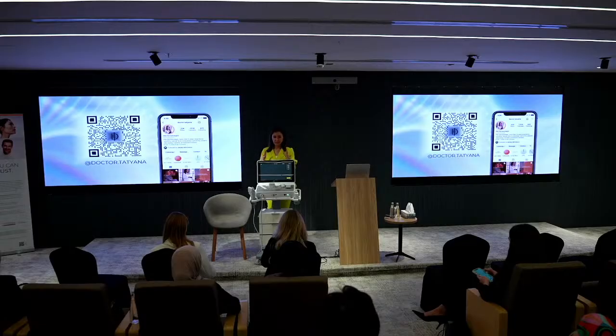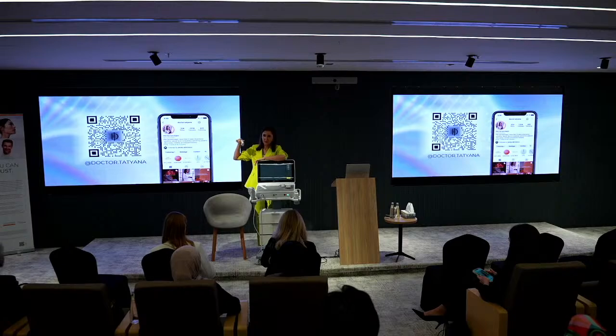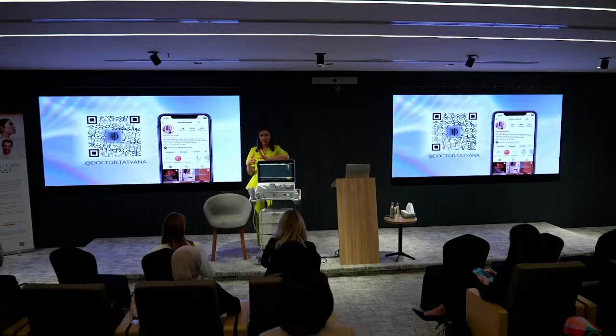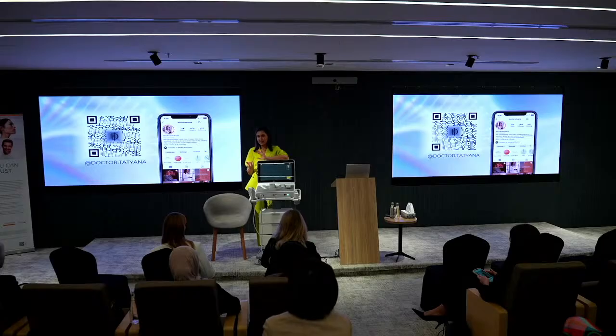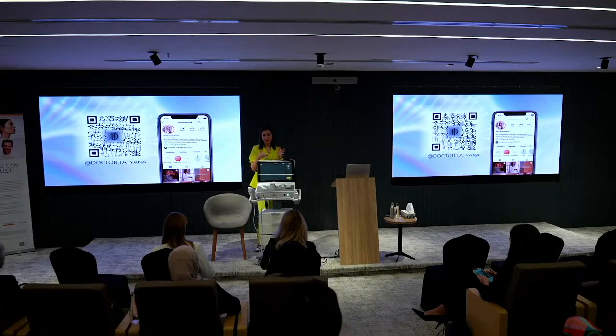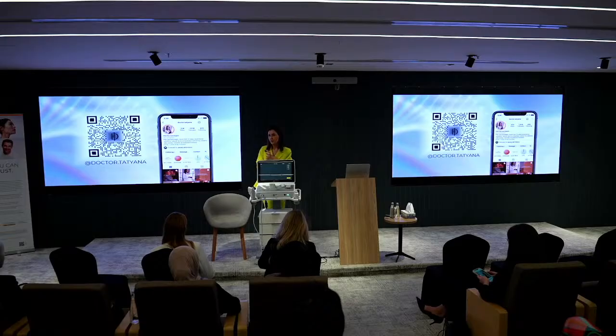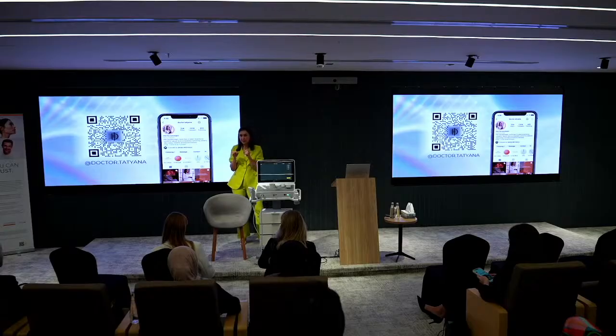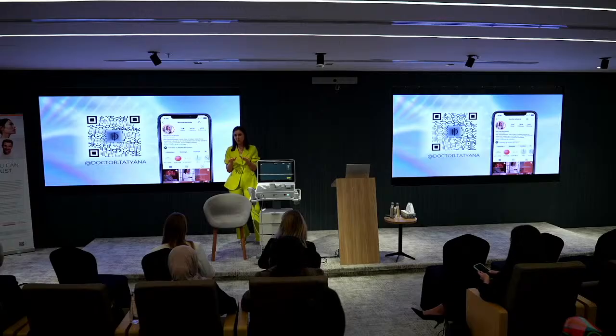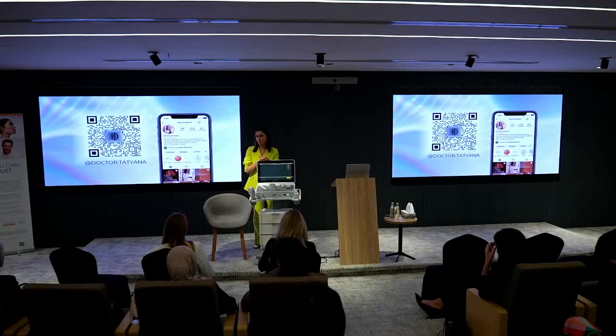So logically, it's here. Transducers have water inside. When transducers are expired, there is some kind of loss of water in the transducer. The best case scenario is that it will affect the visualization. The worst case scenario is that it will affect, again, the penetration of ultrasound in the tissue. For that reason, if it's possible not to use them, don't use them, because you will not be sure that you are at the exact depth that you want to deliver thermocoagulation.